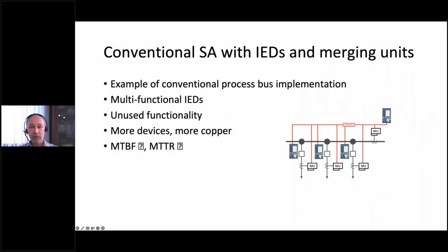In this example, we see a conventional process bus solution with merging units and IEDs. Each of these merging units provides a sampled value stream, and the IEDs use these streams for their protection functions. Often a single IED is used per bay. Apart from the needed functionality, these IEDs might also contain unused functions. And because some process functionality is also located in the IED, additional copper wires might be needed.